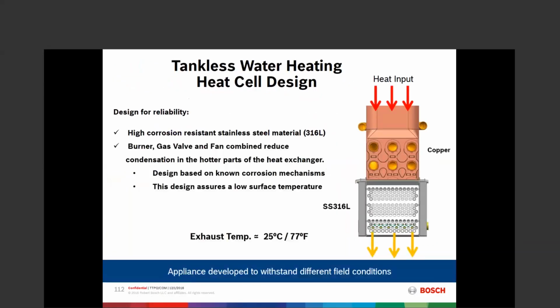Then this gives us a cutaway, a cross section of what exactly is happening inside of these heat exchangers. So we have our heat input, our burner pushing down from the top. All the while, the water is counterflowing. So the cold water enters the bottom left-hand side of the condensing heat exchanger. And the water empties into a bay or a header, however you want to think about it. And leaving that header are these 50 very small tubes. So this is our bank of tubes. These 50 tubes make up the first pass for water through the condensing portion of the heat exchanger.